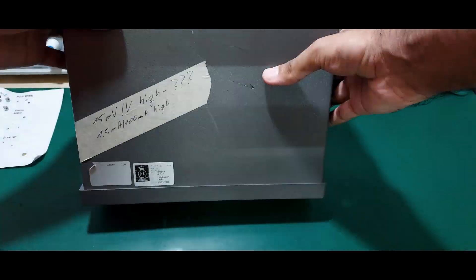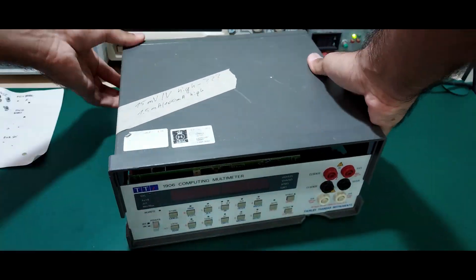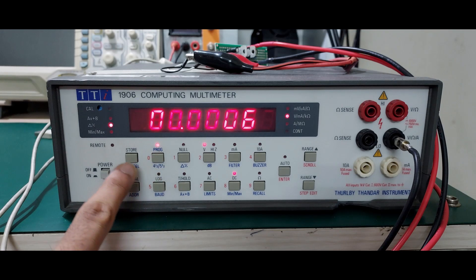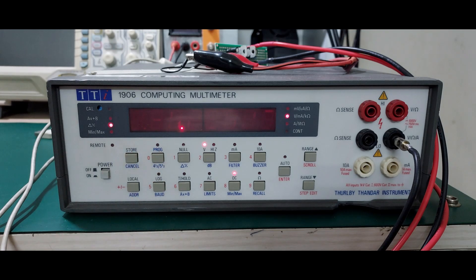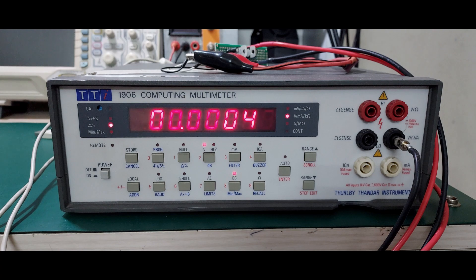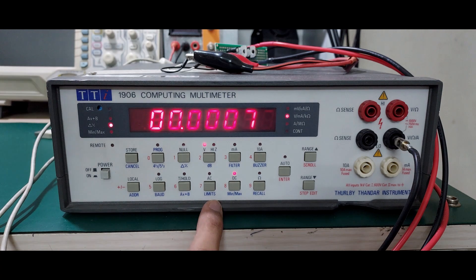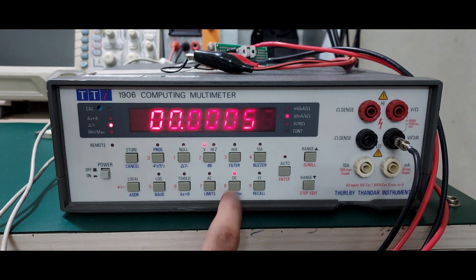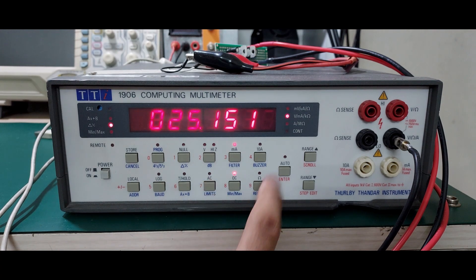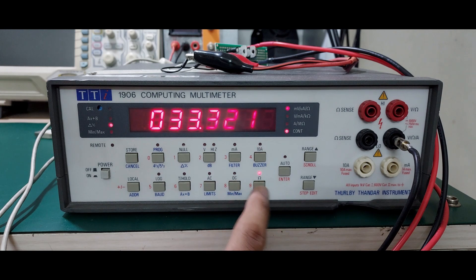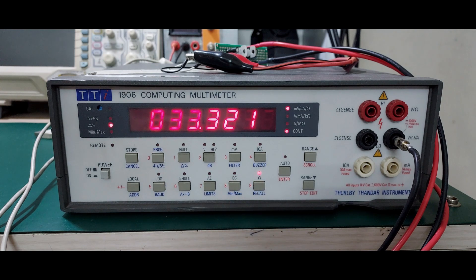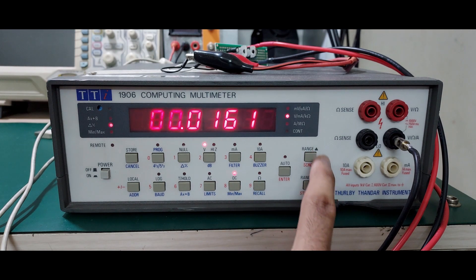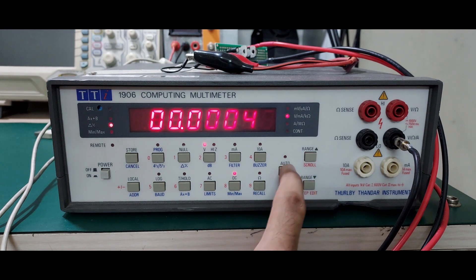Now with everything back in place, it's time to find my way around the meter. Pressing program and cancel to bring the meter to a known state would be a good starting point. The function switches work just as expected. Volts AC and DC, milliamps AC and DC, 10 amps AC and DC and resistance. The ranges for each function can be set manually or automatically.